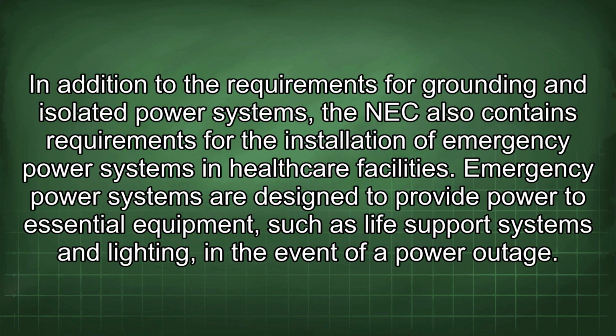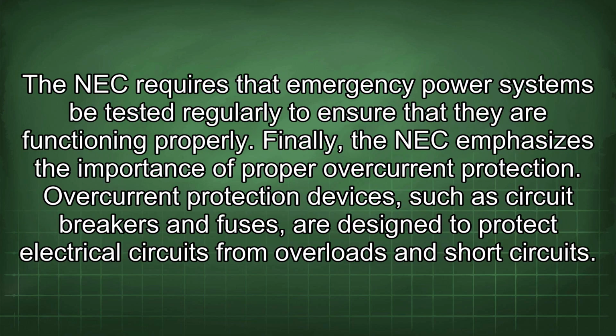In addition to the requirements for grounding and isolated power systems, the NEC also contains requirements for the installation of emergency power systems in healthcare facilities. Emergency power systems are designed to provide power to essential equipment such as life support systems and lighting in the event of a power outage. The NEC requires that emergency power systems be tested regularly to ensure that they are functioning properly.